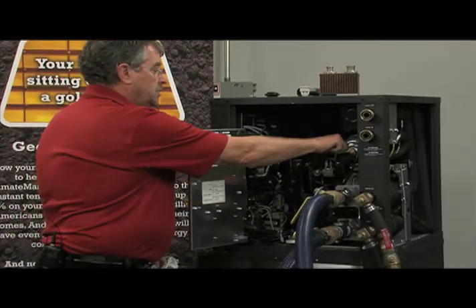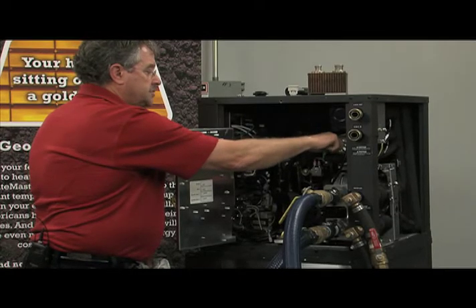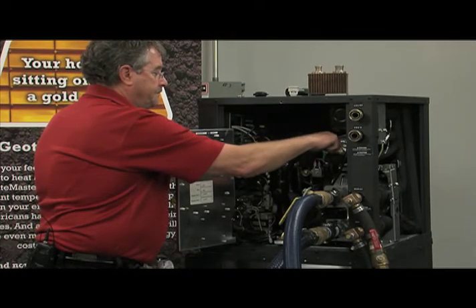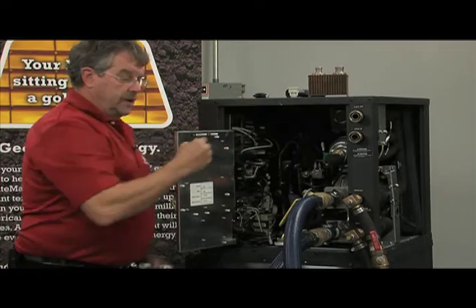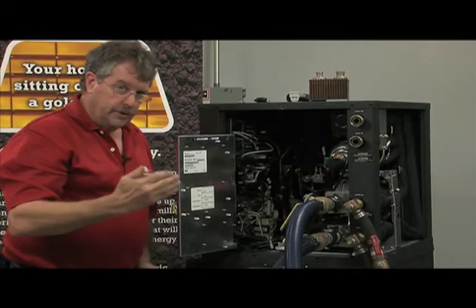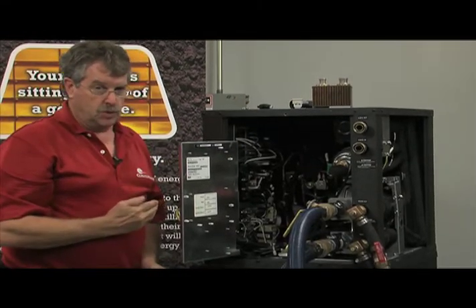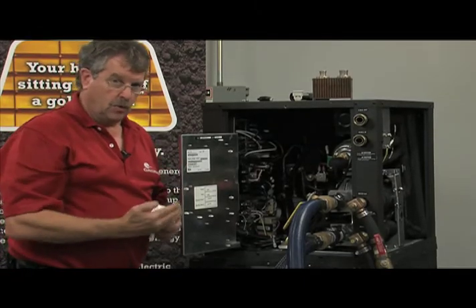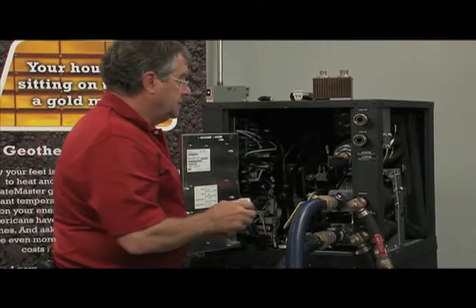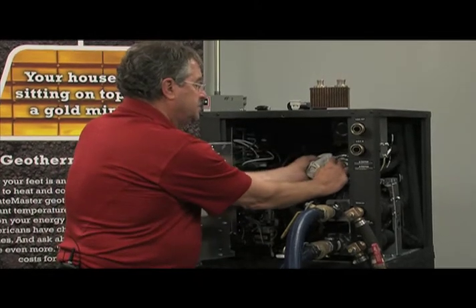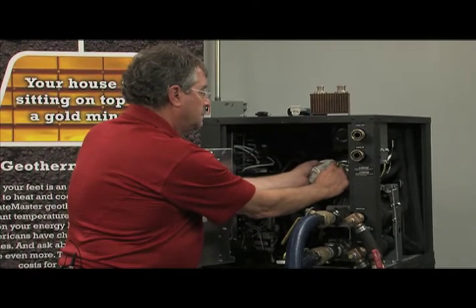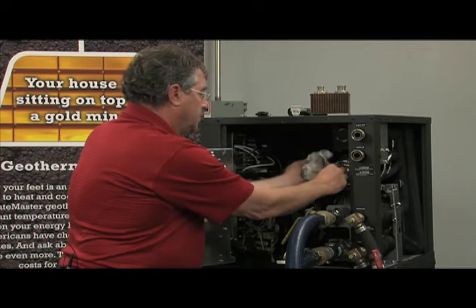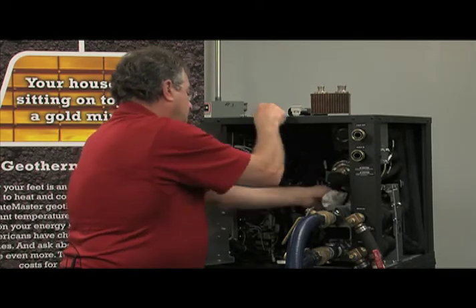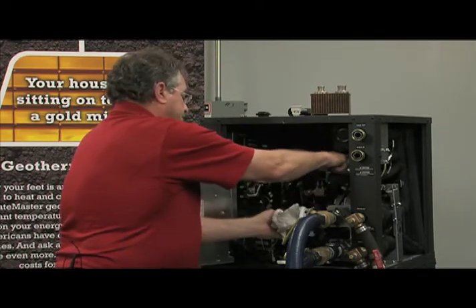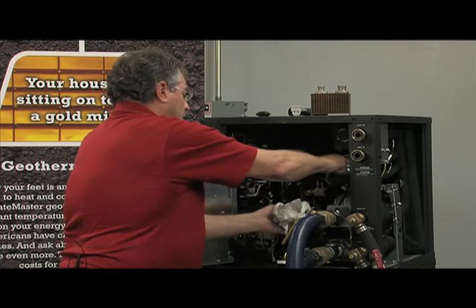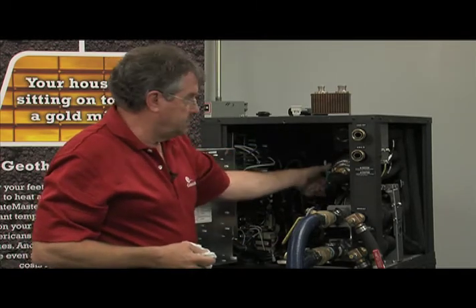So I'm going to remove this tire Schrader cap. Again, I want to emphasize, only with the power off, and it's been off every bit of 20 minutes. You don't do anything on the wet side with power on to these units. I'm going to go ahead and burp this. Okay, I'm in good shape there. Clean it up, put my cap back on. Now I'm ready to pressurize my expansion tank.